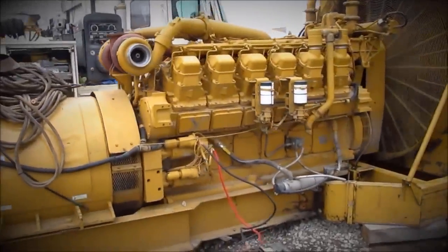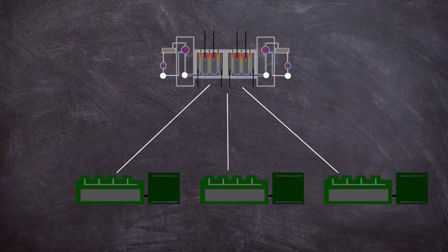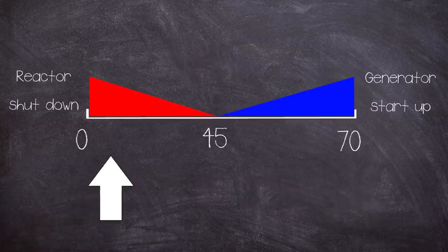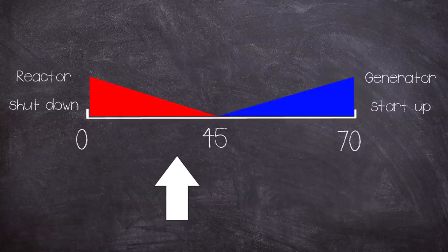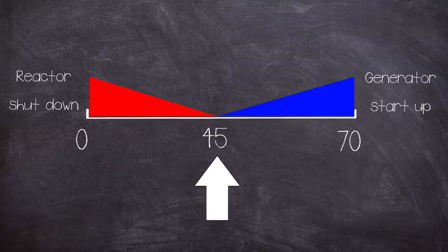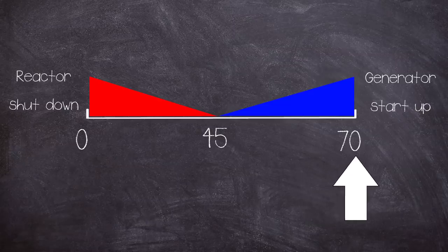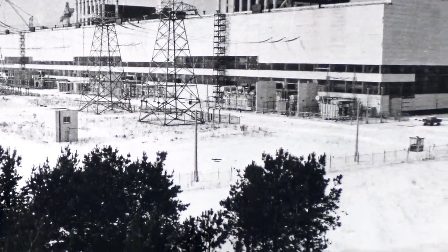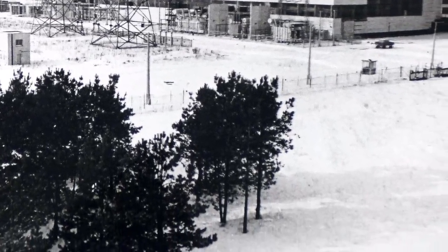Well the solution is pretty simple and that is a diesel backup generator. Each of Chernobyl's reactors had three backup diesel generators which took in excess of 70 seconds to reach full power. Too much time in the event of a full power cut. In theory some of this time could be covered by the spool down of the turbo generators which was theorized to cover around 45 seconds. Not the full time needed but possibly enough to prevent fuel melting. To prove that this could work it had to be tested out and in 1982, 1984 and 1985 this was attempted but all tests failed to produce the electricity needed to run the pumps. The test was to be conducted again in April 1986.